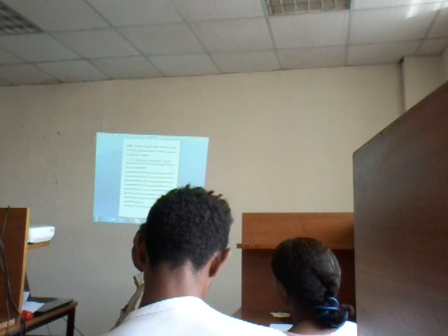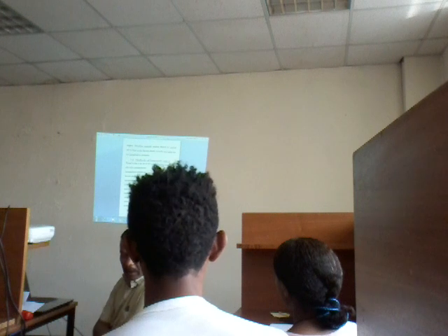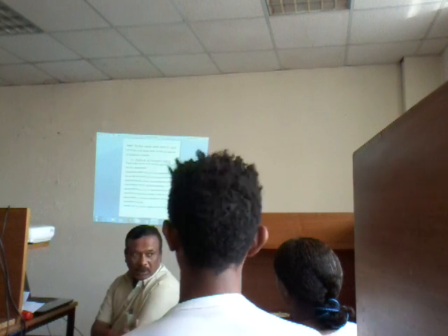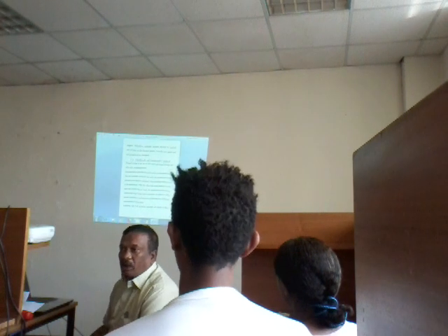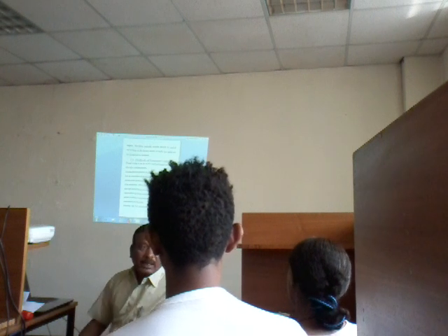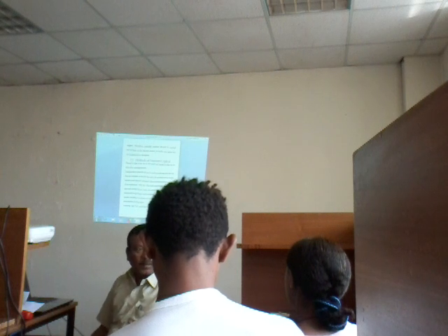While this will probably mean adhering to a somewhat more rigid schedule than previously, the return in reduced demand charges and possibly energy charges can be considerable. So while controlling the maximum demand, we may also switch off some loads, which is possible for reducing the maximum demand. So in addition to the MD charges reduction, it is also possible to reduce the kilowatt hour consumption. So what are the loads? First, what are the loads that are running non-essential? For example, in a textile industry, a communication plant or some pumps can be switched off during the very peak times, not adversely affecting the production or anything else.